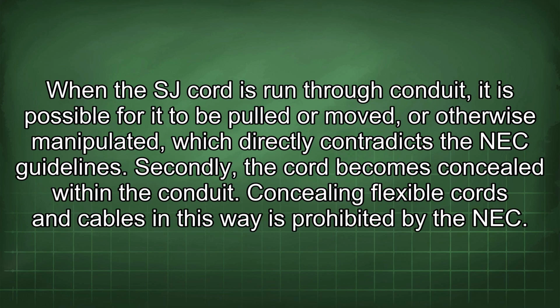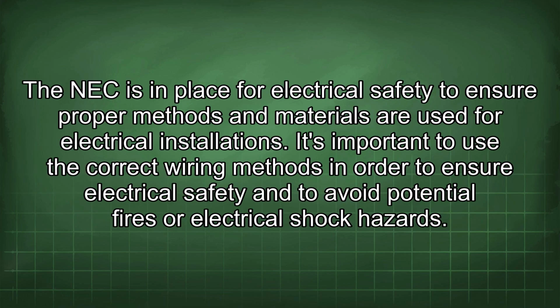When the SJ cord is run through conduit, it is possible for it to be pulled or moved or otherwise manipulated, which directly contradicts the NEC guidelines. Secondly, the cord becomes concealed within the conduit. Concealing flexible cords and cables in this way is prohibited by the NEC. The NEC is in place for electrical safety to ensure proper methods and materials are used for electrical installations.